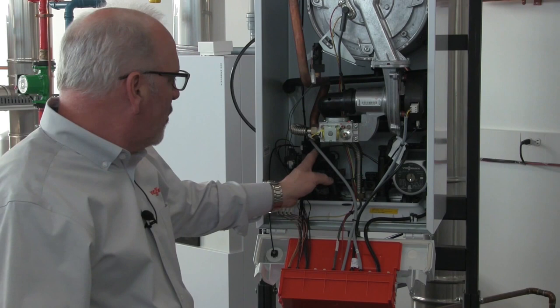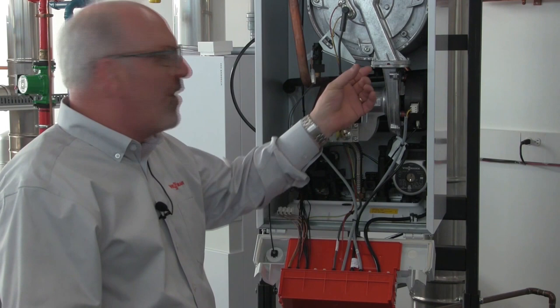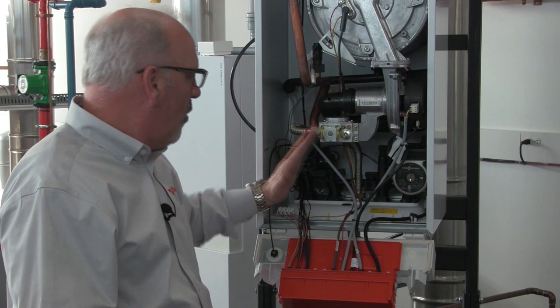The controller also operates a three-way diverting valve, so we can divert our boiler water to space heating or, on a call for domestic hot water, to the tank. The Vitodens 100 comes with a domestic hot water tank sensor. When domestic hot water comes on, we will divert the three-way valve, and this circulator pump will either drive domestic hot water to the tank or space heating. Again, very simple operation on that. We've actually taken the wiring down to a three-point appliance plug. Simple wiring as well.